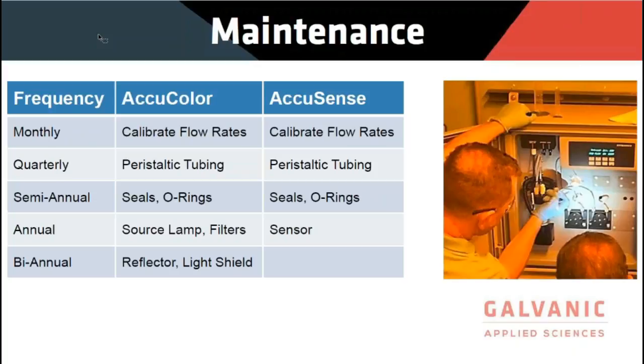And then if you have a colorimetric analyzer, you want to change out your source lamp and filters about every 1 to 2 years. Then every 2 years you'll probably want to change out the reflector and the light shield, versus a potentiometric analyzer where the sensor is probably something you'll want to change out every 1 to 2 years.